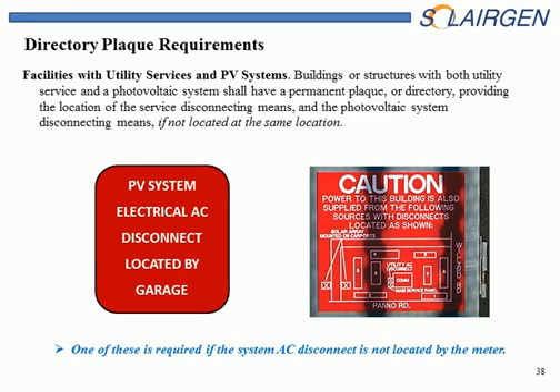The NEC requires this plaque, of course, if the disconnect is not located next to the utility meter. And of course, this would probably be the same disconnect that the utility would require. So it'll either be a plaque that clearly states where it's located, or it would be a directory showing a map to it. There's no standard on this, so you may see a variety of different labels trying to indicate where this is.